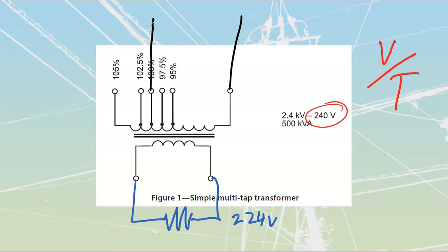This is where we were originally, had 224 volts. If I'm at the 100% tap, that would mean I'm at a 10-to-1 transformer ratio going across to this side over here. Which means that if this is 224, this side over here would have to be 2,240 volts.